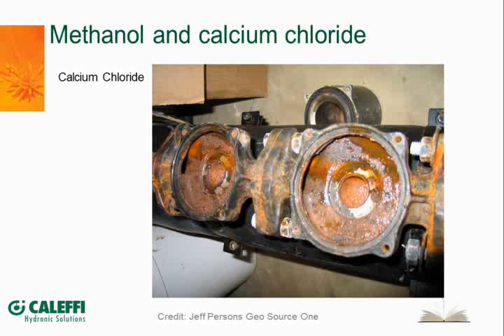Even if the methanol was mixed with a good quality water, like deionized or demineralized water, it still doesn't have the inhibitors. One of the inhibitors they put in propylene glycols is to lock up that hardness and some of those bad things in the water that you blend it with. It's not to protect the glycol, it's to protect the water being blended in at the job site. So unless you're buying pre-mixed, where they've mixed it at the factory with deionized water, the chemicals in the glycol are there to lock up those problems, and you don't see that in the methanols.